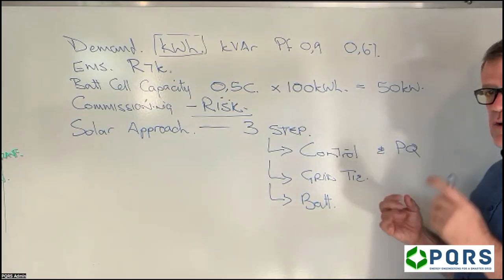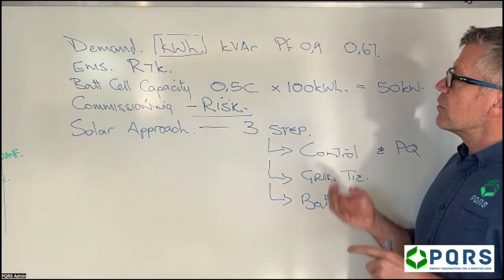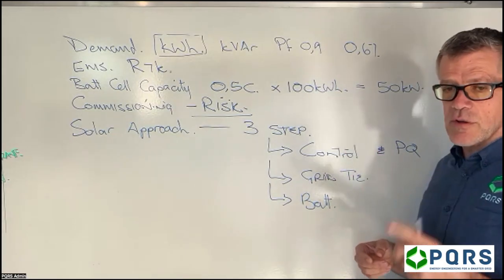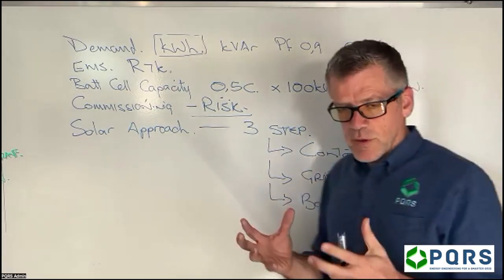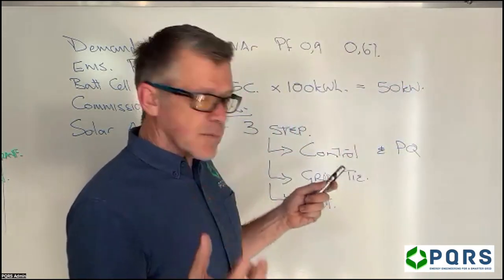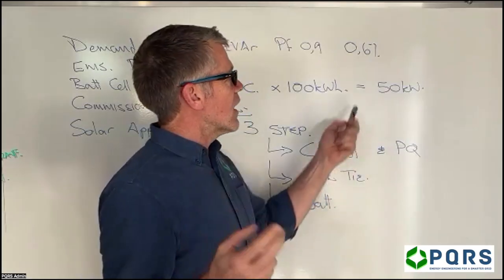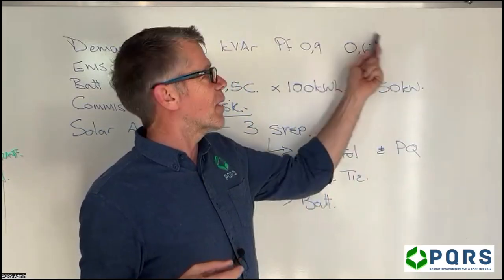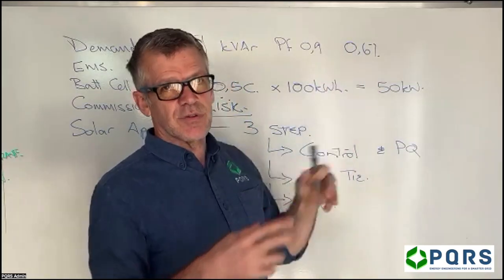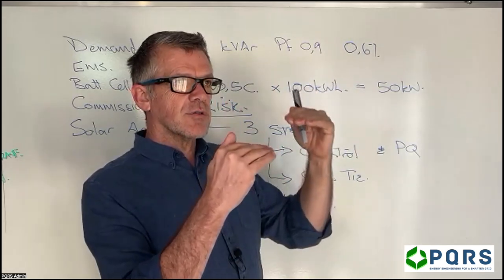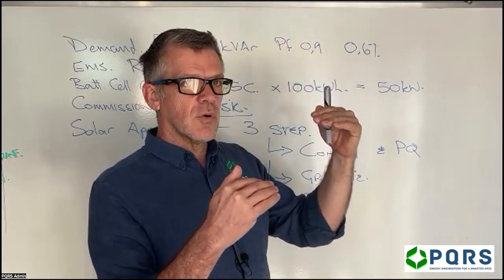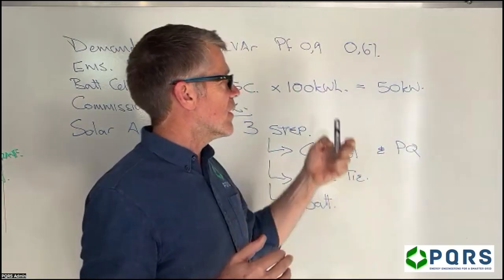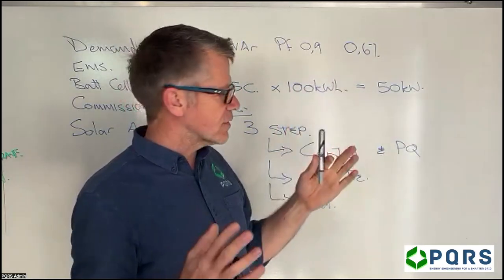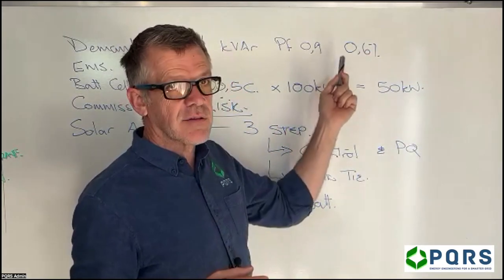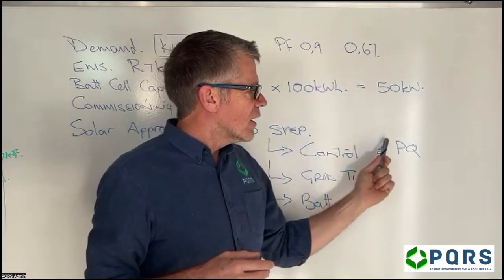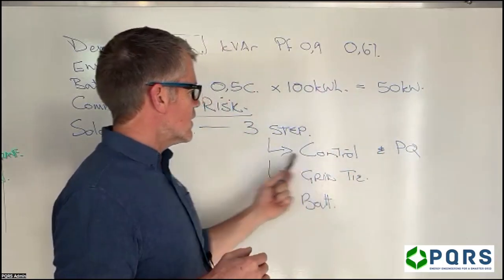This is going to include monitoring and measuring your power factor and your harmonic component. I'm almost convinced you have some sort of harmonic component. You'll see over weekends specifically, your power factor drops substantially as a ratio to what is on or what is running at the time. Now, when you have a solar system, the solar is not going to take the reactive component away. So you want to sort out the reactive component in this process.